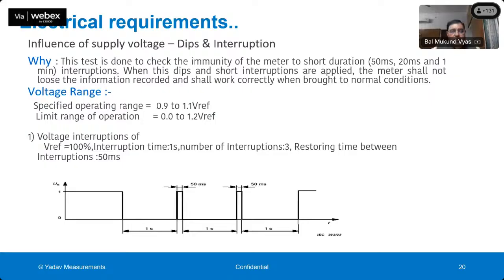Another test requirement for an electricity meter is how it behaves when there is a voltage dip or interruption. The meter should be able to withstand supply interruption or voltage dips. Sometimes voltage can dip up to 50%. Sometimes it can be interrupted for a few, let's say 1 second, and then restore. Under such very quick interruptions, the meter should not get damaged. It should work correctly once supply is restored, and its data should not be corrupted. So data should be maintained. That's the requirement for supply voltage dips and interruption.